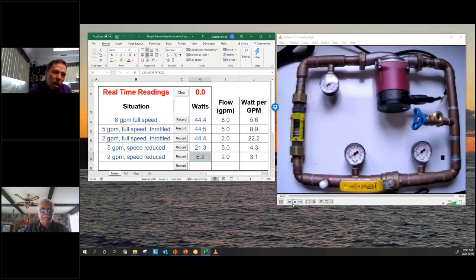If you have a throttling valve and there is no VFD and the throttling valve is fully open, it is very likely that you're over pumping your system. Somebody saw a throttling valve, heard it was not good to have a throttling valve partially closed, and opened it up. What happens then is that your flow will increase and you will not be saving. So not having a closed throttling valve does not mean you have no savings potential. Very often that means you've got too much flow.